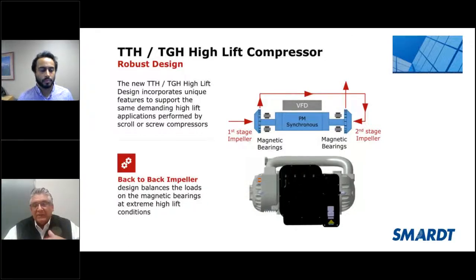Anytime you get the lift, it's really the difference between the liquid evaporative temperature on the cooler and the condensing temperature on the condenser. So you put on top of that low flow. Now you have low flow, low saturation temperature, and higher condenser temperature. Now you really have a lift issue, right? And you have to have the ability to maintain that lift and operate over the whole entire portfolio, or I should say the platform and that compressor map. Well, they've done a really good job of combating that.